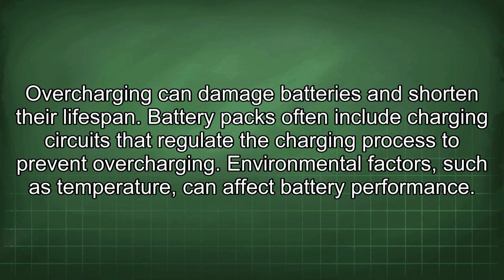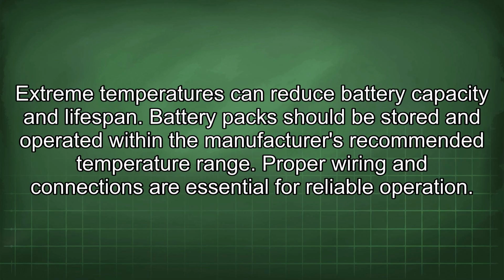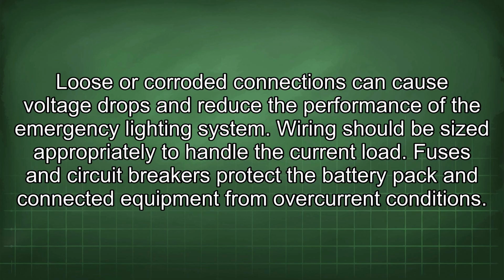Environmental factors, such as temperature, can affect battery performance. Extreme temperatures can reduce battery capacity and lifespan. Battery packs should be stored and operated within the manufacturer's recommended temperature range. Proper wiring and connections are essential for reliable operation. Loose or corroded connections can cause voltage drops and reduce the performance of the emergency lighting system.